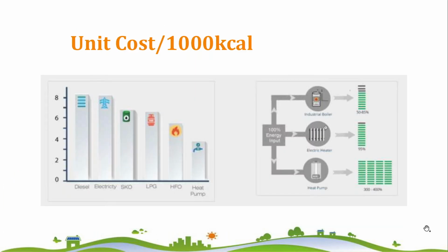The COP of the heat pump varies from 2 to 6 depending on the temperature requirement, refrigerant, and application nature. So what does that number mean? Suppose your COP is 4: for every 1 kilowatt of electrical input, the heat pump generates 4 kilowatt of thermal energy. When you look at an industrial electric heater, for every 1 kilowatt of electrical input, the heater generates around 0.95 kilowatt of thermal output. For a boiler, the efficiency of the system is around 50 to 90%, depending on the fuel.